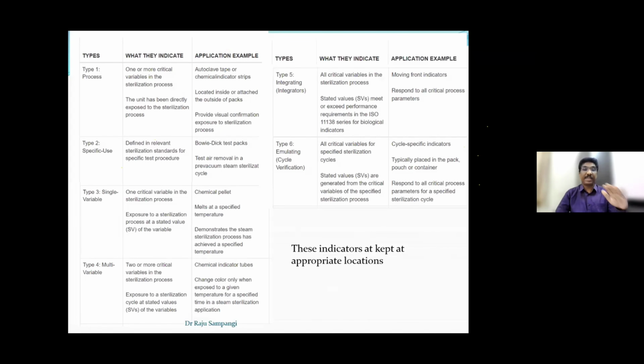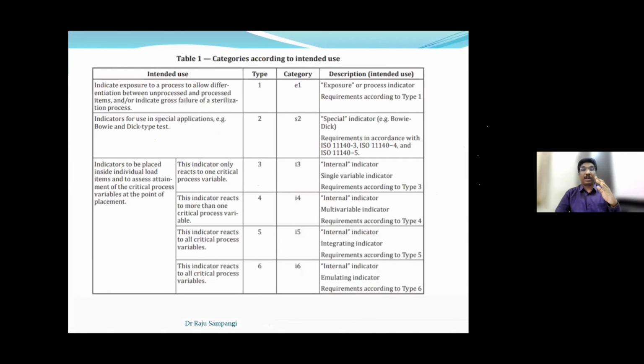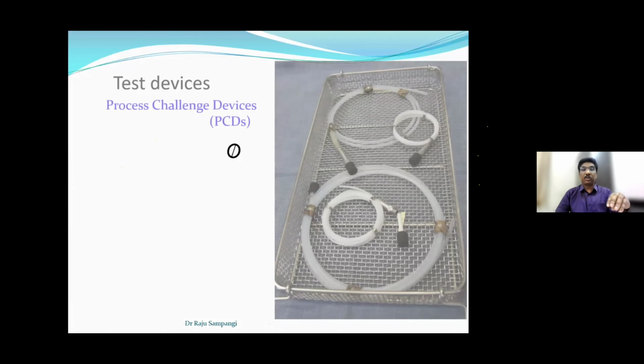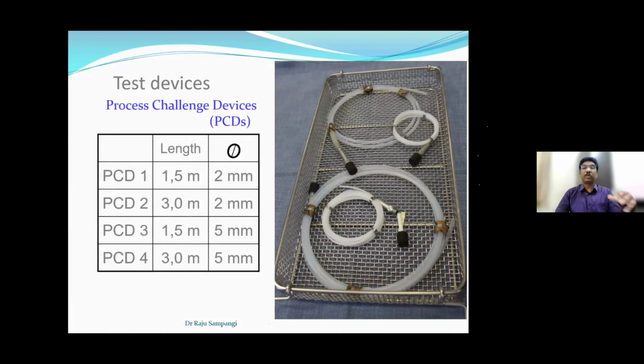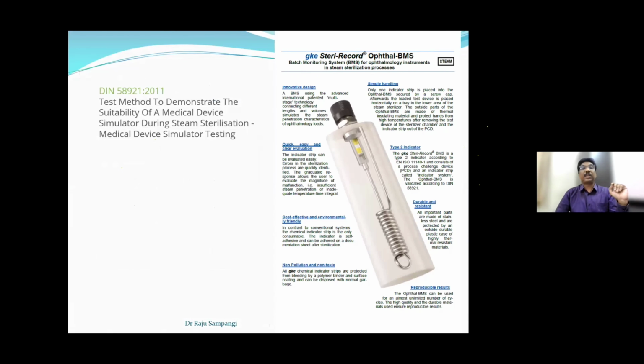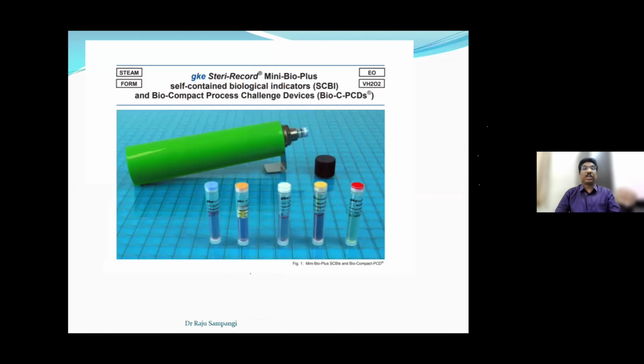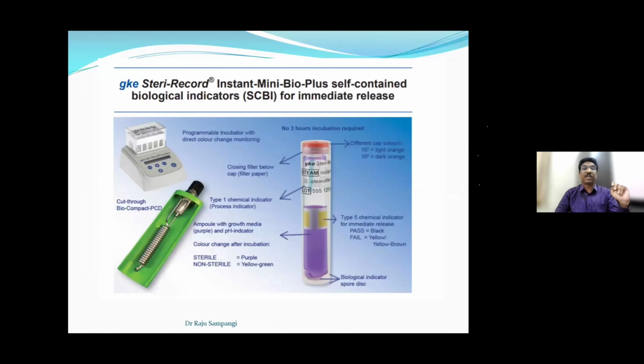Like a type 1 indicator just indicates that this load you have put in has passed through the sterilization step. That's all. But it will not give anything extra above that. So there are various categories or types of indicators which you have to use for specific purposes. And you may also have to use process challenge devices like what you see here, depending on whether you're using a reusable tubing or not. These are the others recently in the market. This is the Ophthal BMS from GKE, wherein you can use an emulating integrator and indicator inside this, which will emulate a phaco handpiece. And the other ways to do this, the indicators that we use are the biological indicators. This is the self-contained indicator along with a PCD, which can be used for monitoring your sterilization processes.